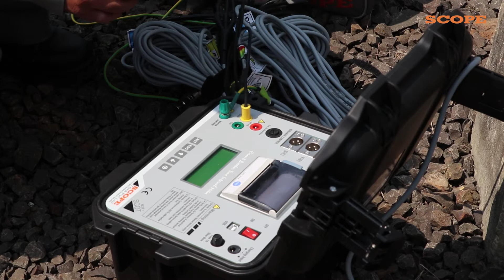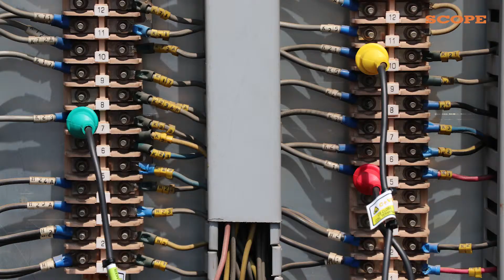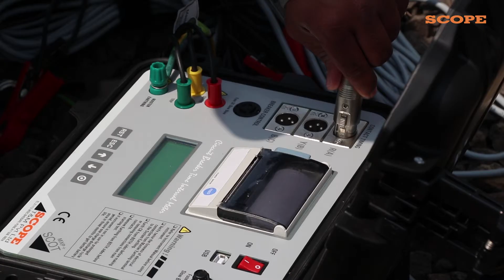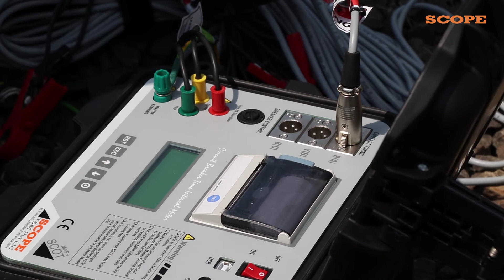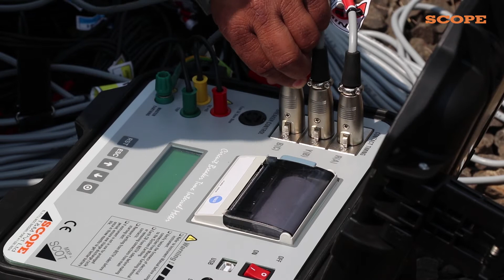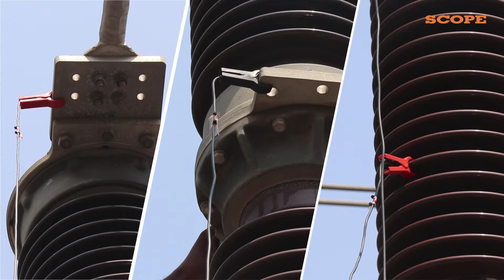The breaker control cable is connected to the breaker control section and the other end is connected to the command panel from where the command is initiated. Connect R, Y and B testing cables in the respective timing measurement channels. Each testing cable has 3 terminals, 1, 2 and common terminal.